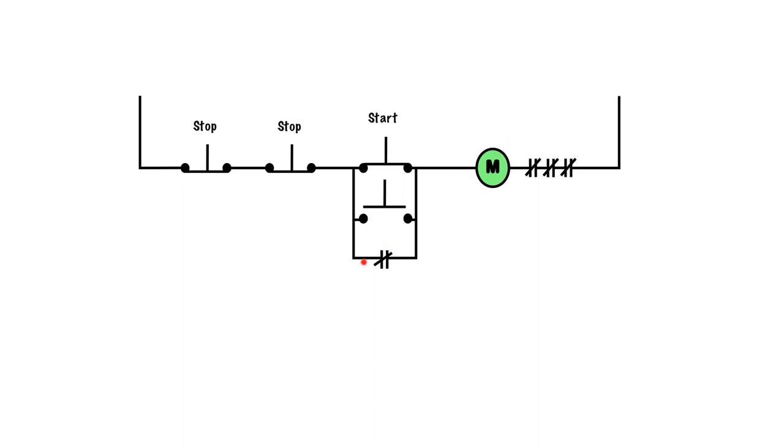M coil is physically attached to these contacts. So whenever these energize, these will close. When we let go of the pushbutton and it springs back to the normally open position, it now has a complete path that goes through the normally open contacts and energizes M as well, so it can be held in or sealed in.